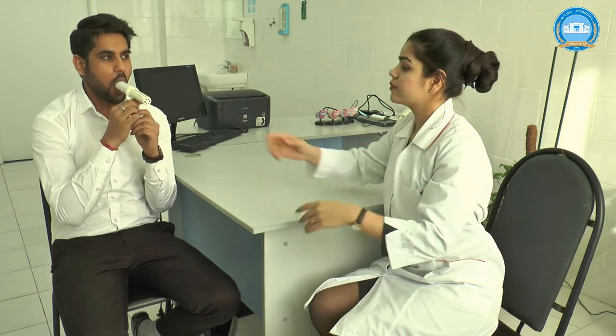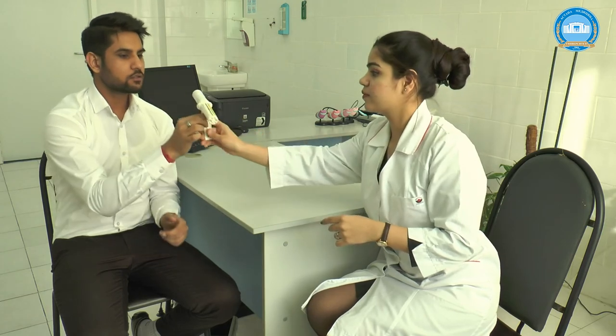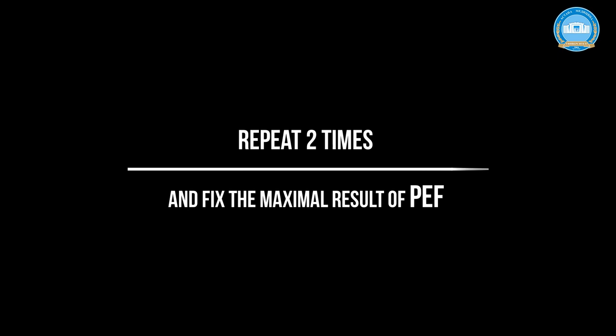Then we record the value on the scale at which the pointer stopped, repeat the procedure two times, and record the maximal result in the diary.